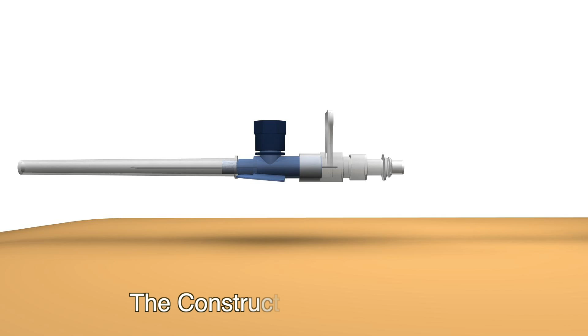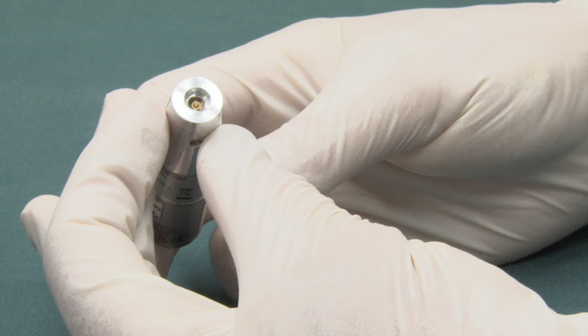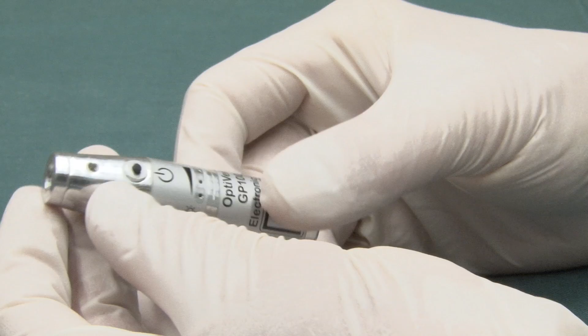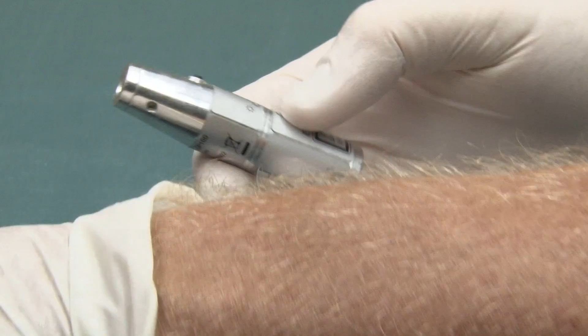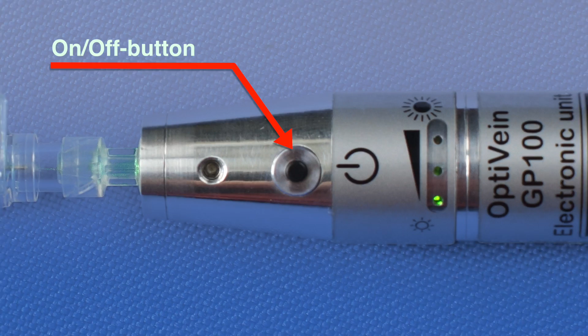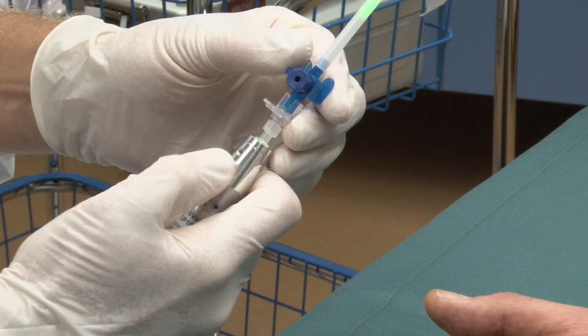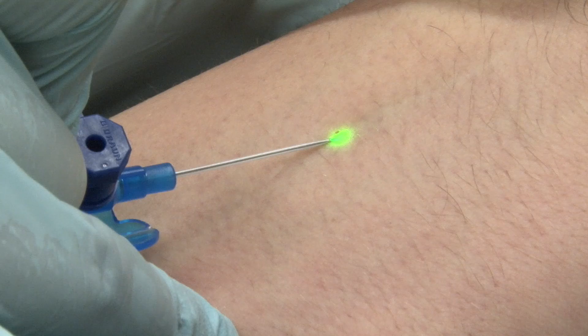Attach the electronic unit to the catheter by rotating the electronic unit until it is firmly attached to the catheter adapter. Press the on-off button for 1 second to activate the light of the electronic unit. Notice that the laser safety mechanism, shutter, prevents the electronic unit from emitting laser light if the catheter is not connected to the electronic unit. To change the brightness of the laser light, shortly press the on-off button. The clinician can choose between 3 levels of brightness of the laser light. As a general rule, light-colored skin and superficial veins require lower brightness of laser light.